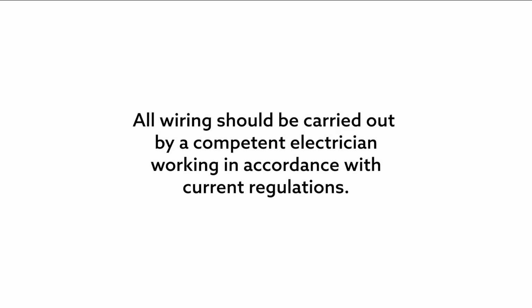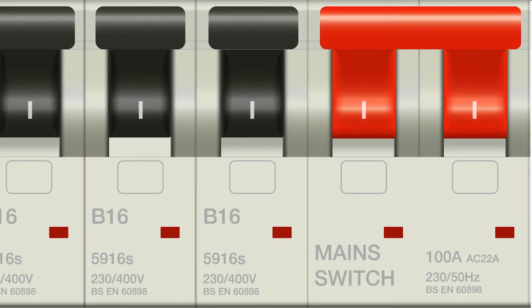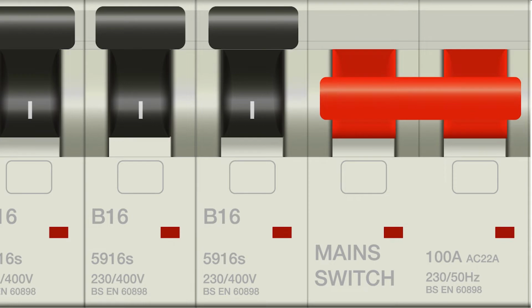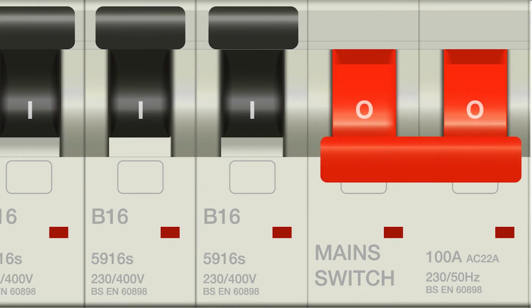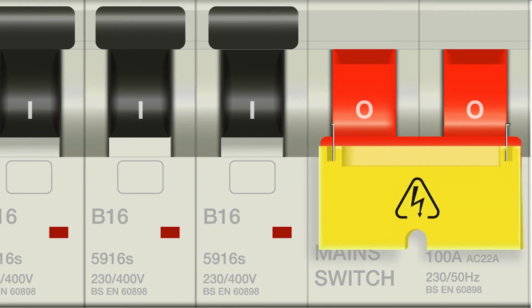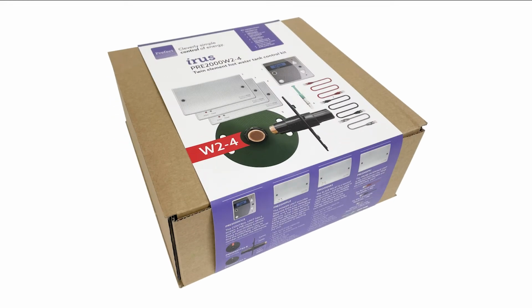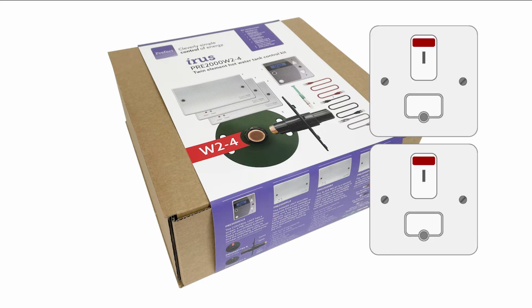All wiring should be carried out by a competent electrician working in accordance with current regulations. Identify the appropriate power supply and perform procedures to ensure the circuits are completely isolated. The supply should be locked in the off position, and safe working practices should always be observed. Our retrofit water tank kit contains all you will need to control an existing twin-element hot water system, except for 2 double-pole switches for isolating the control equipment from the main supply.